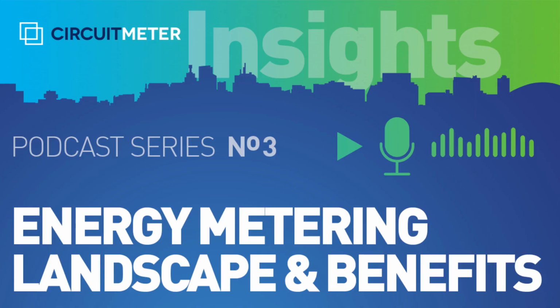But for this kind of forensic analysis, 3 are really foundational: real power, power factor, and maybe the most critical one, operating time on. Okay, break those down. Why those 3? How do they impact the bottom line? Well, real power tells you the actual useful work the equipment is doing. Power factor, though, tells you how efficiently it's using that power. So a struggling machine might have a low power factor. Exactly, it draws power less cleanly, you could say. And that struggle, reflected in a lower power factor, is often the very first warning sign of a mechanical problem brewing, or just general inefficiency setting in.